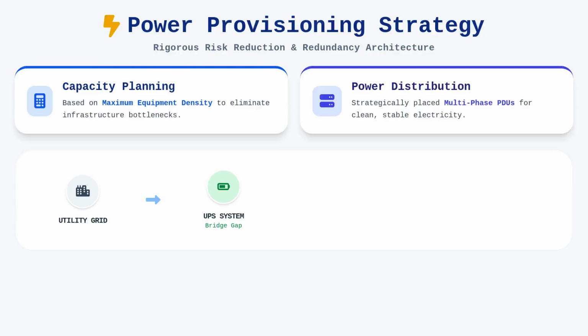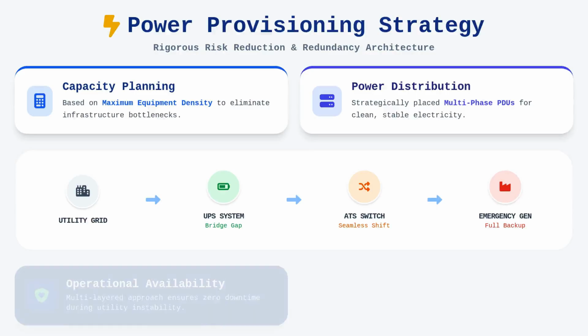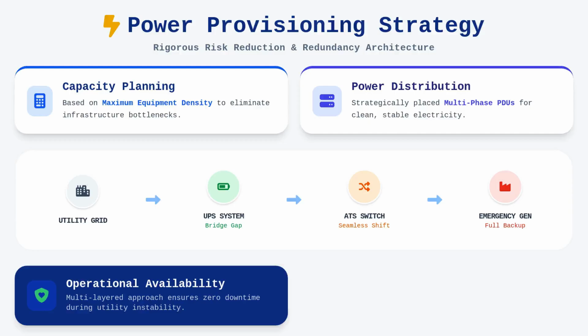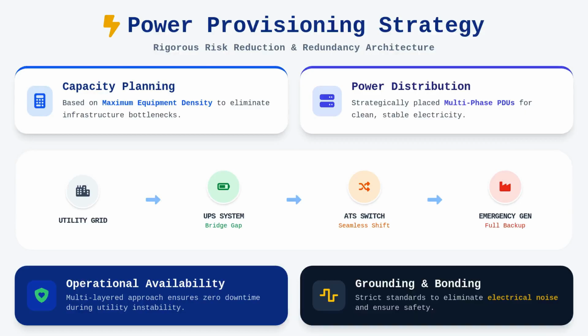Beyond the UPS, the transition to emergency generator power must be seamless, achieved through automated transfer switches that isolate the internal load from the utility grid during outages. This multi-layered approach ensures that even in the face of local power instability, the equipment room maintains operational availability. Grounding and bonding requirements must be strictly adhered to alongside these electrical setups to ensure safety and prevent electrical noise from interfering with data transmission.